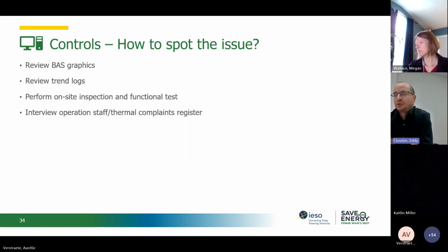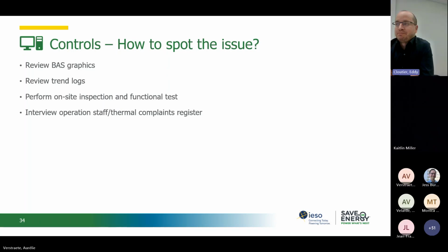Next, we'll talk about control measures. As Megan said earlier in the presentation, control measures are among the most common in existing building commissioning. And there are almost as many types of measures as there are systems and ways of programming them. Several methods will make it possible to determine which measures are applicable. First, simply viewing the control graphs will often allow you to notice anomalies such as manual control points or problems with temperature, humidity, or pressures.